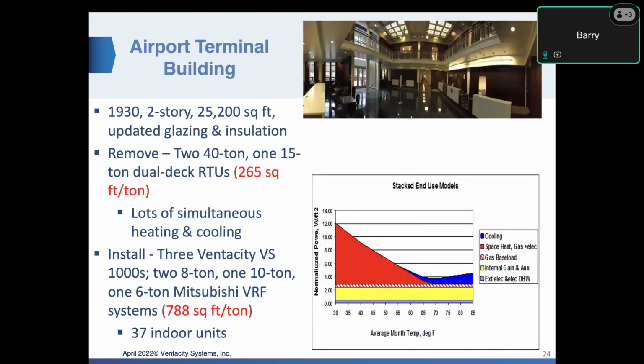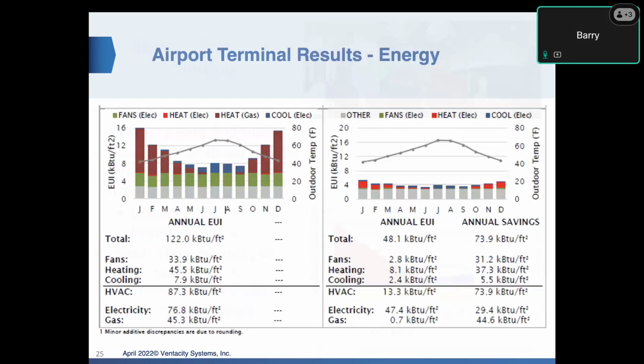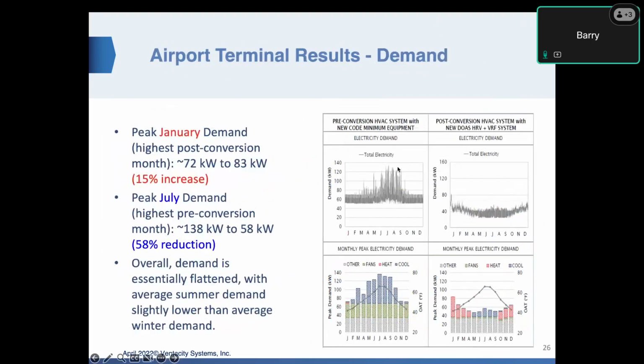So this is the airport terminal building. Very quick. It was dual deck RTUs, and I want to show you the graphs. Again, electricity went from 76 to 47, gas 45 down to pretty close to 0. They have some domestic hot water, a little water heater for the bathrooms there. But there's demand. You can see demand went from very high peaks up over 120 to the peak at around 60. So we cut demand in half on that project.